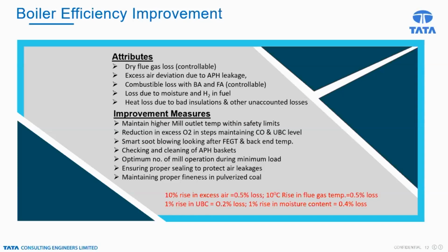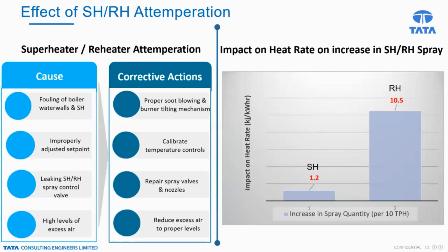And because of deterioration, there will be degradation of various systems over a period of time. There will be some impact on the boiler efficiency. But the point here is, if you want to get a better plant heat rate, you have to operate the boiler as efficiently as possible, taking care of some of the improvement measures specified here.